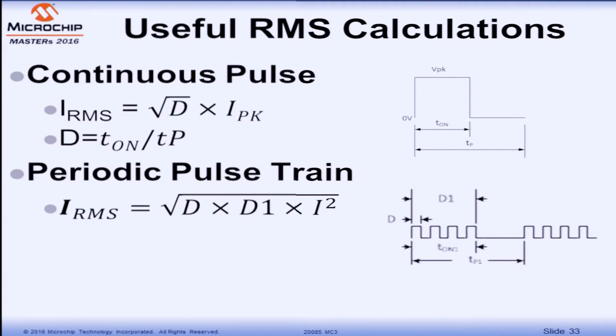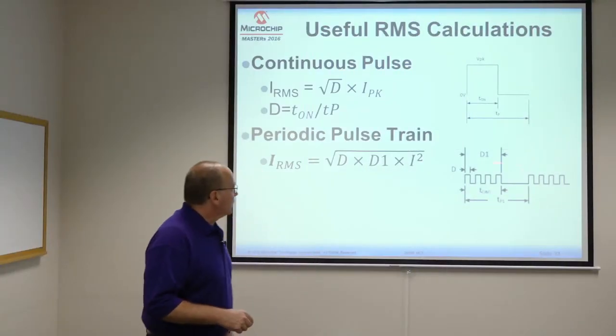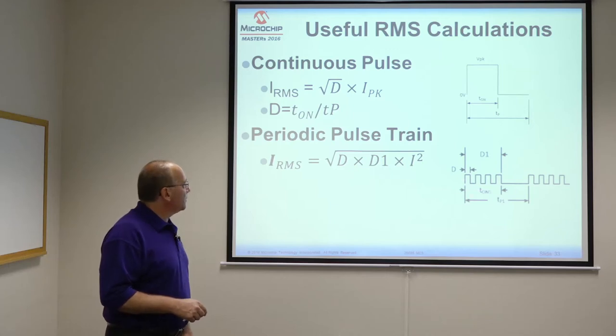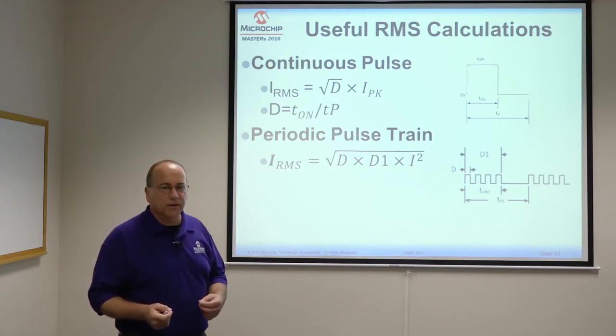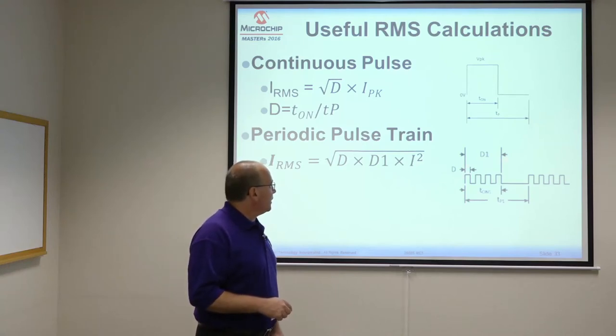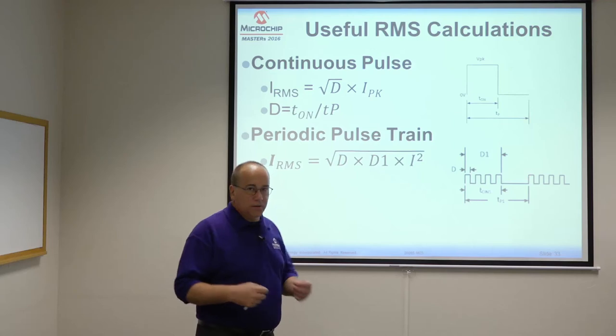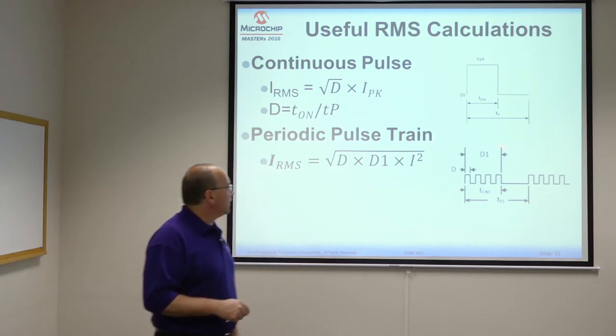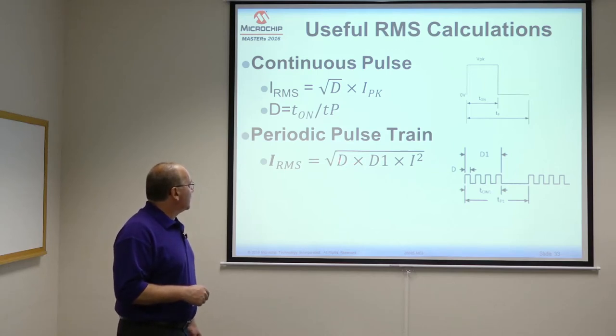For a continuous pulse, RMS current equals the square root of the duty cycle times the peak. But for a periodic pulse train — such as PWM speed control for a three-phase motor where one winding is off for a period — you can look at this in terms of two duty cycles. One is the PWM duty cycle (on time versus switching period). The other is the operation time versus the period of the electrical rotation. Once you calculate these two, you can calculate RMS current using the combined formula.